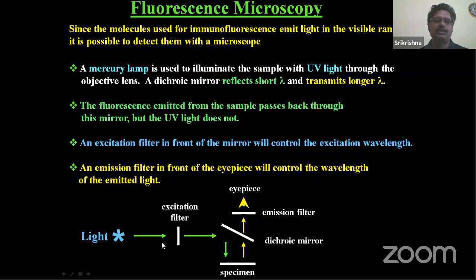when you induce a light source, it passes through an excitation filter and hits a dichroic mirror here. The dichroic mirror has a special property to reflect the light onto the specimen where your objective is kept, and then the excitation of the molecule present in that object will emit light in the form of energy, which is transmitted through this dichroic mirror to the detector, that is the eye, or eyes are also known as detectors.